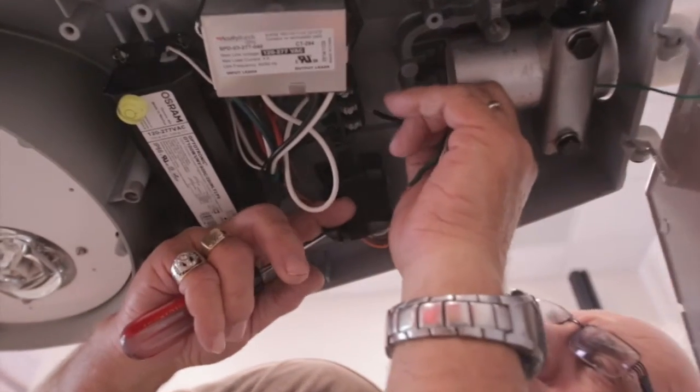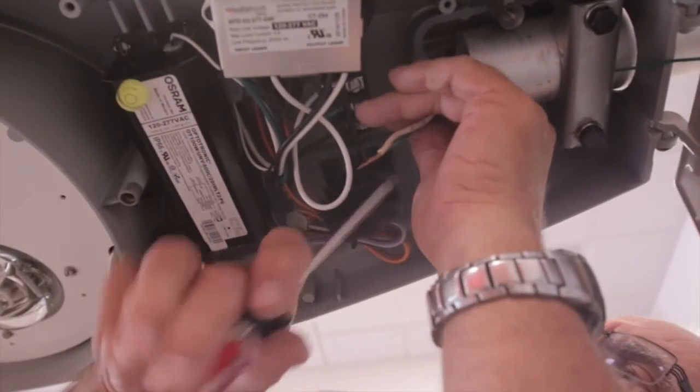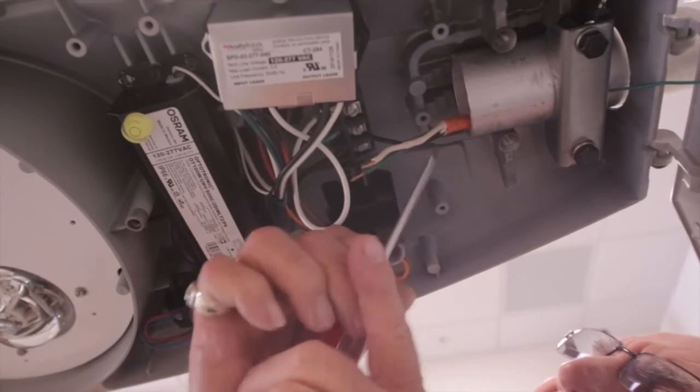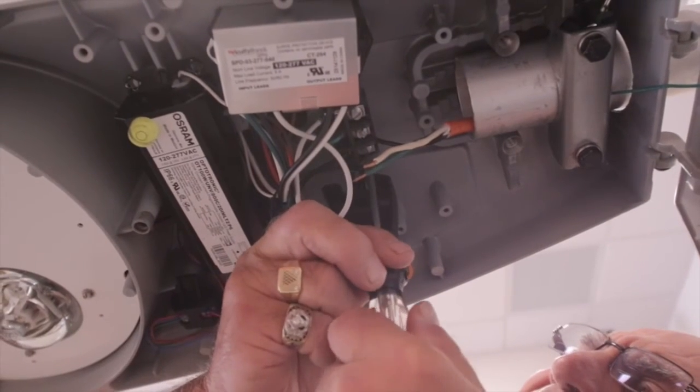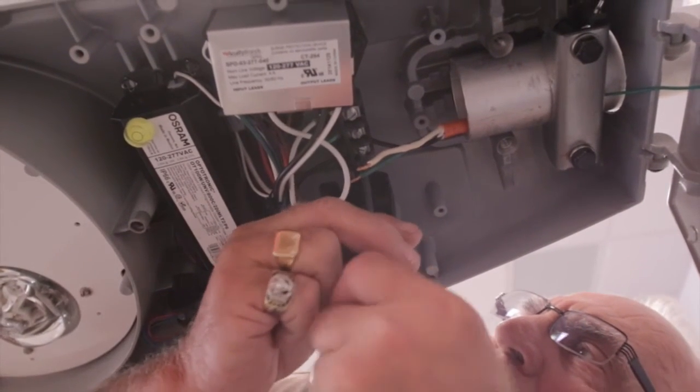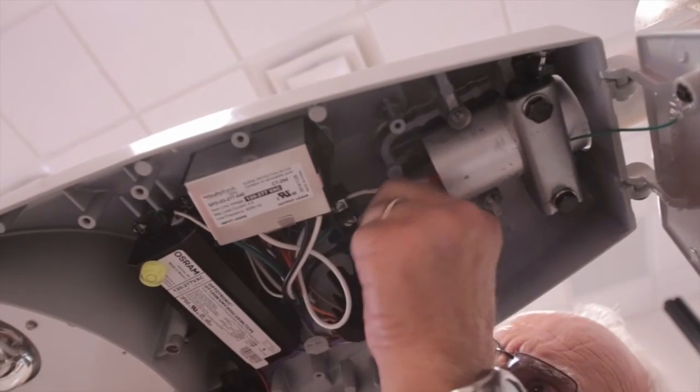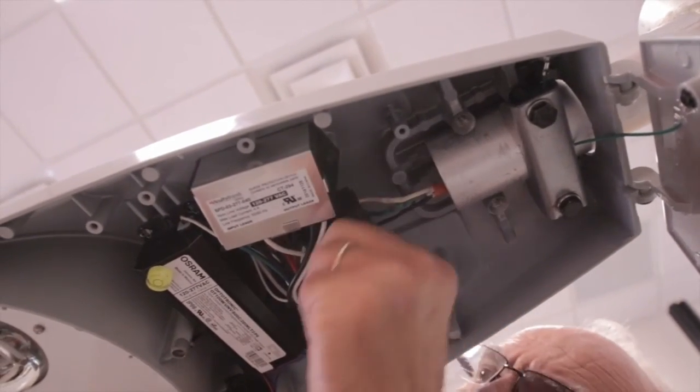Now you're ready to wire the luminaire. Start by loosening the terminal block screws. Then install the color-coded wires: line, ground, and common. Tighten the terminal block screws after you install each wire. Give each wire a gentle tug to make sure it's secure.